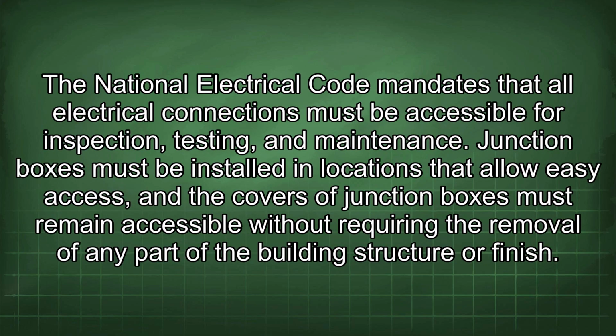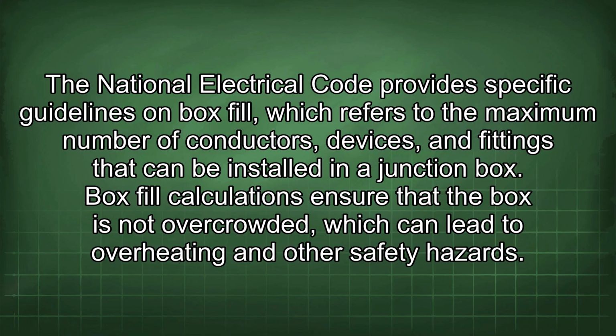The National Electrical Code mandates that all electrical connections must be accessible for inspection, testing, and maintenance. Junction boxes must be installed in locations that allow easy access, and the covers of junction boxes must remain accessible without requiring the removal of any part of the building structure or finish. The National Electrical Code provides specific guidelines on box fill, which refers to the maximum number of conductors, devices, and fittings that can be installed in a junction box.